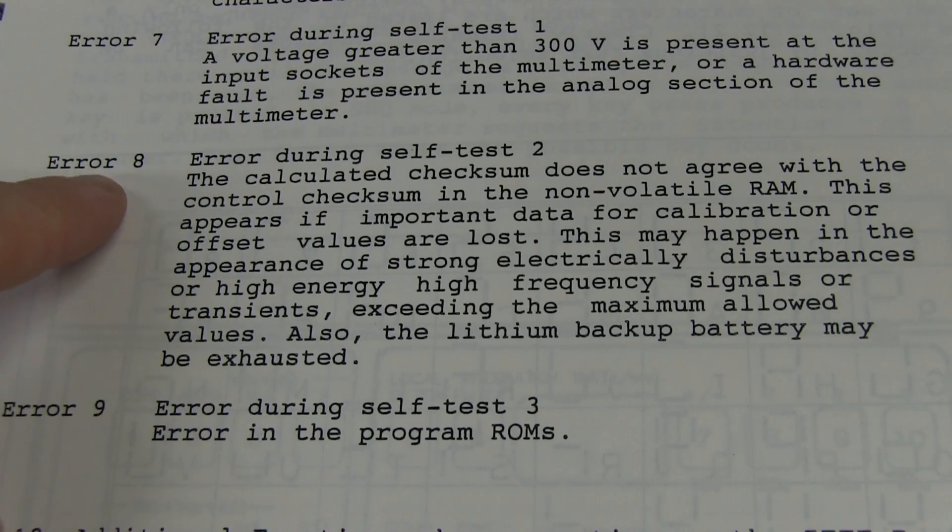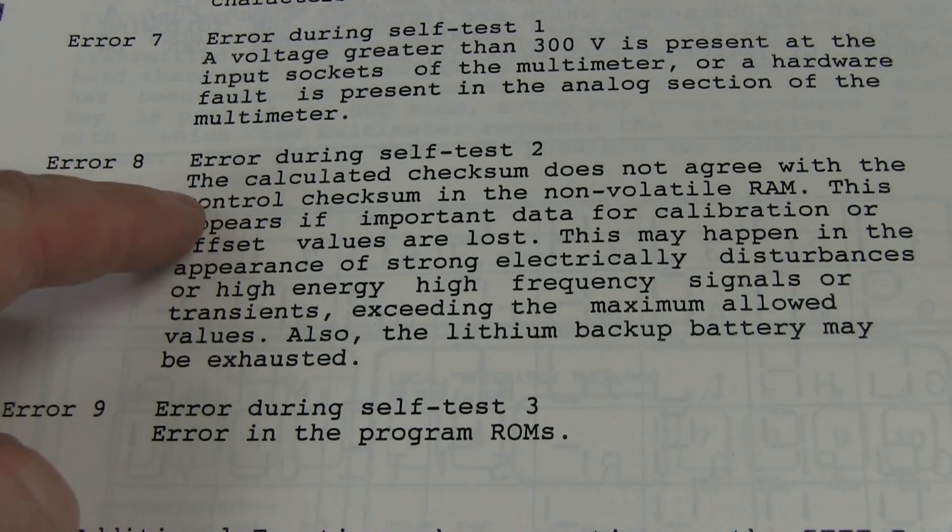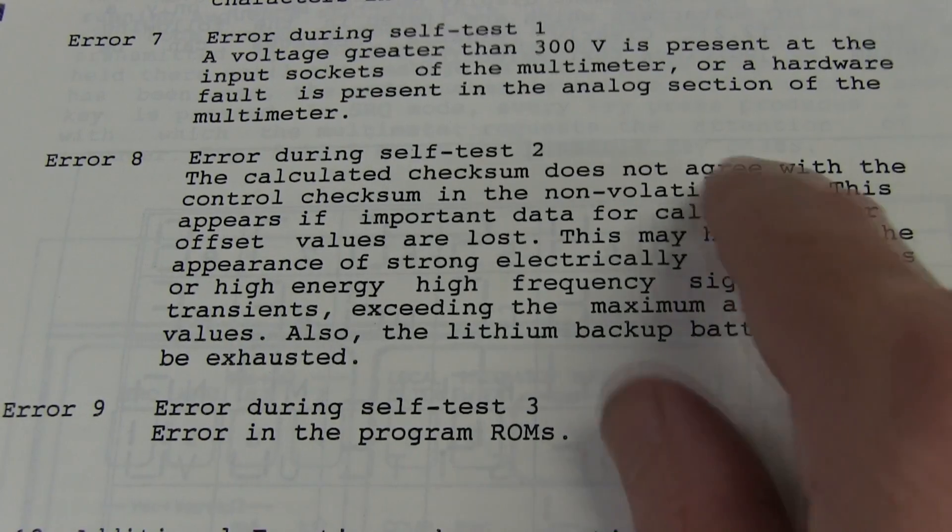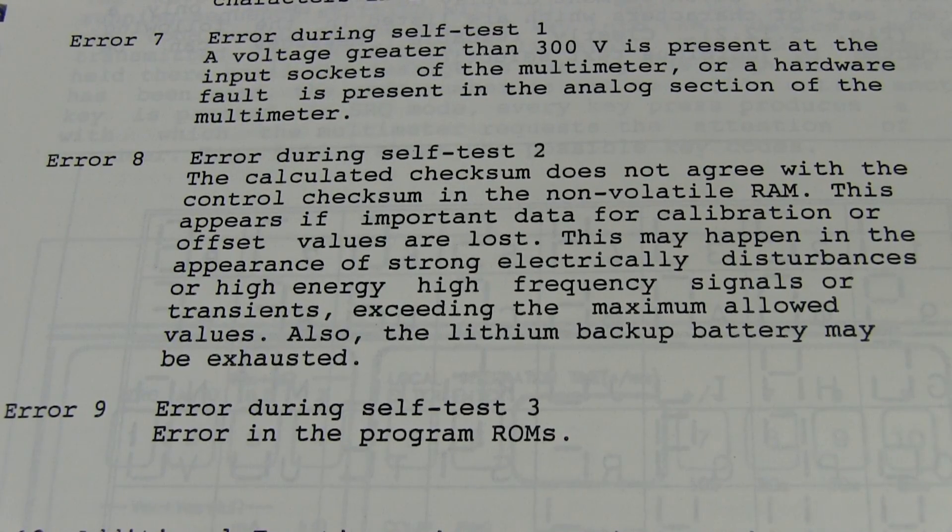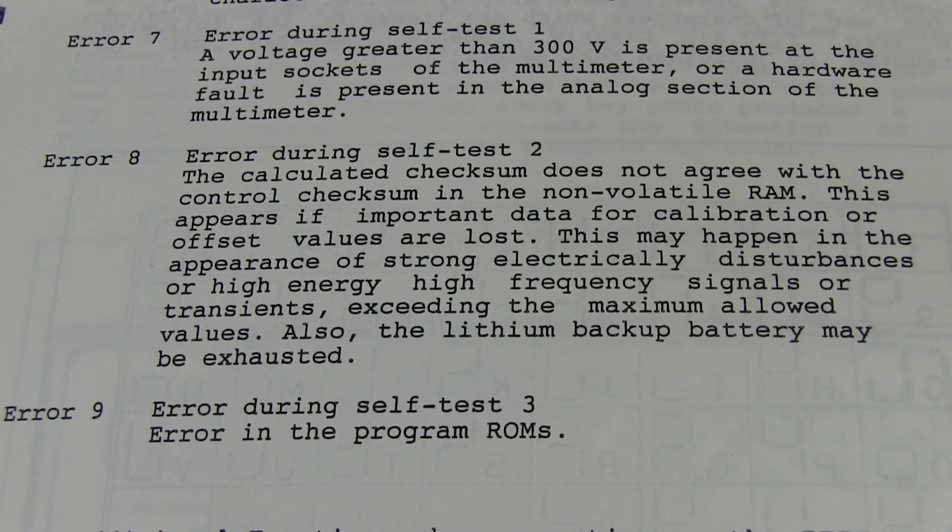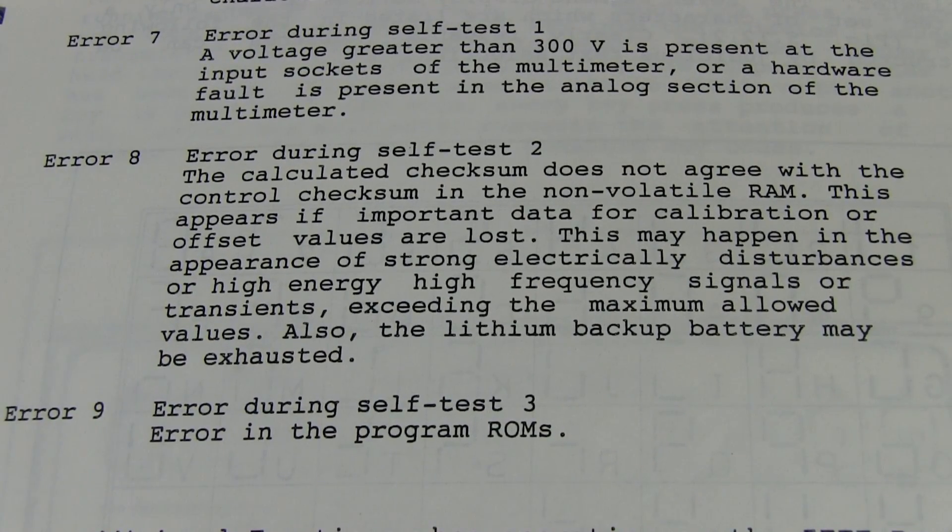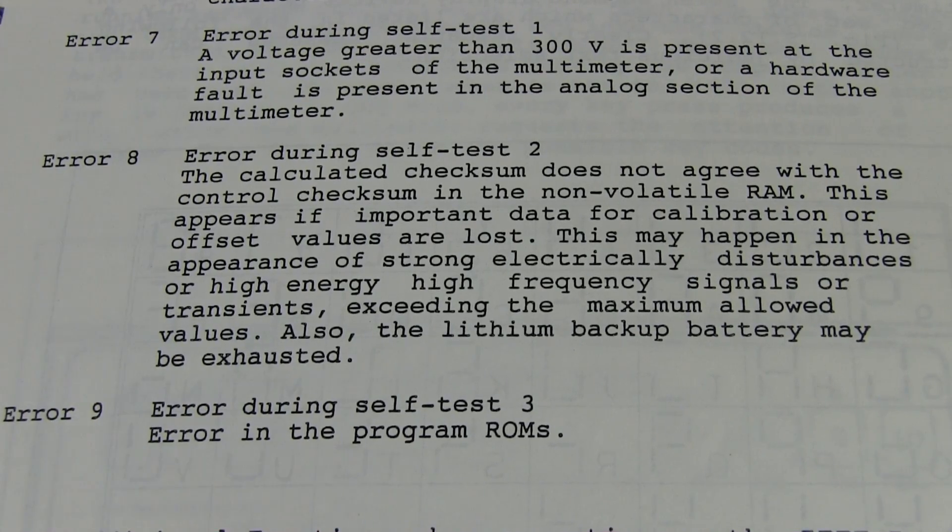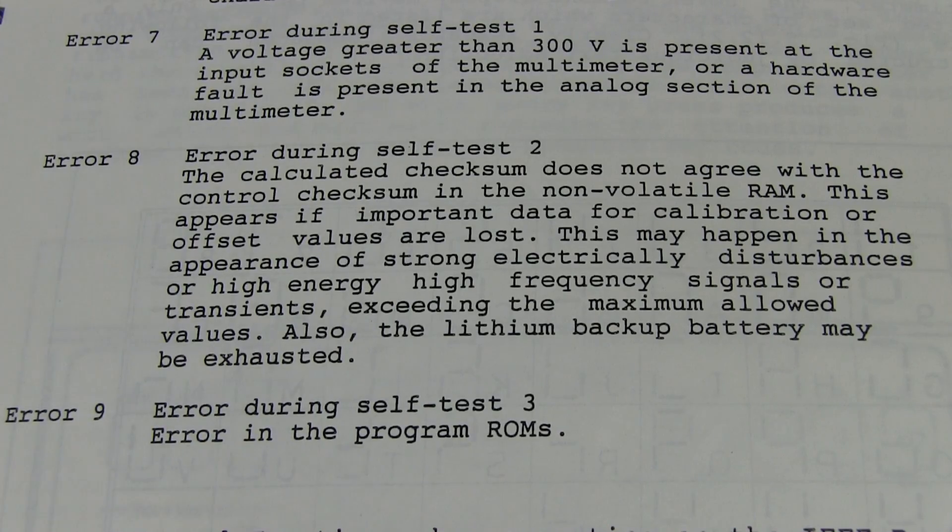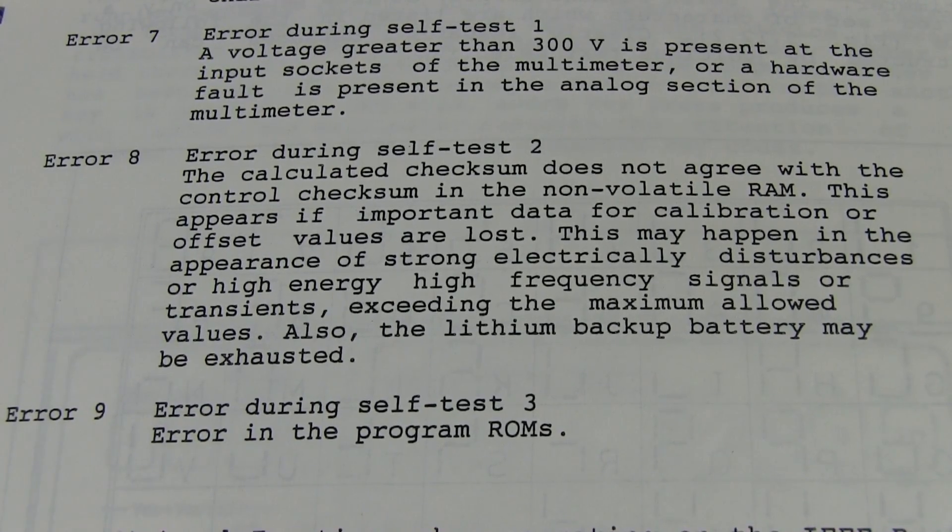I'll have to read the manual, I guess, see if we can get something on error 8. Bingo, there you go, error 8. Error during self-test, it compares as I suspected, it compares the checksum with the one in the non-volatile RAM, that Dallas chip. So obviously for this thing to power up previously, that Dallas chip must still have the correct data in there. Otherwise it would give you an error 8 every time you boot up. So the Dallas chip has to be good.